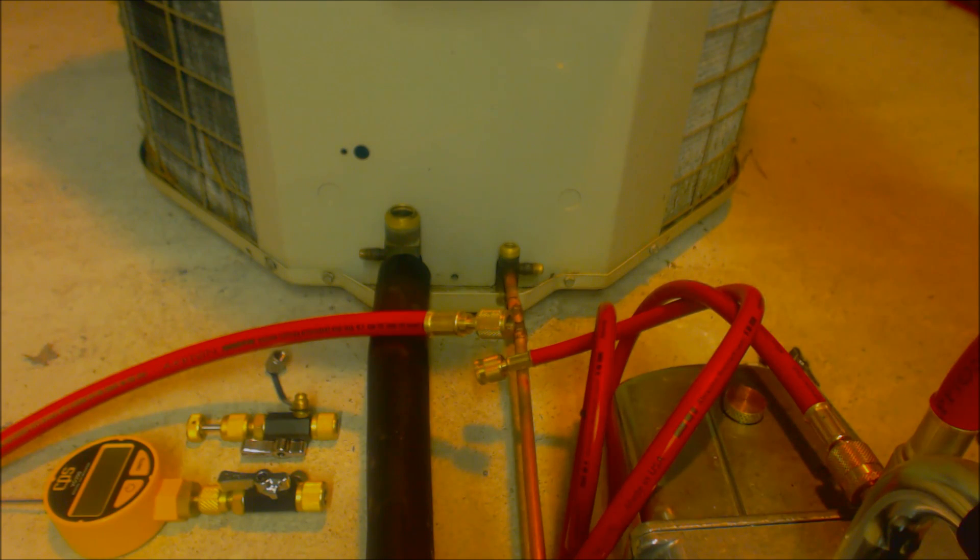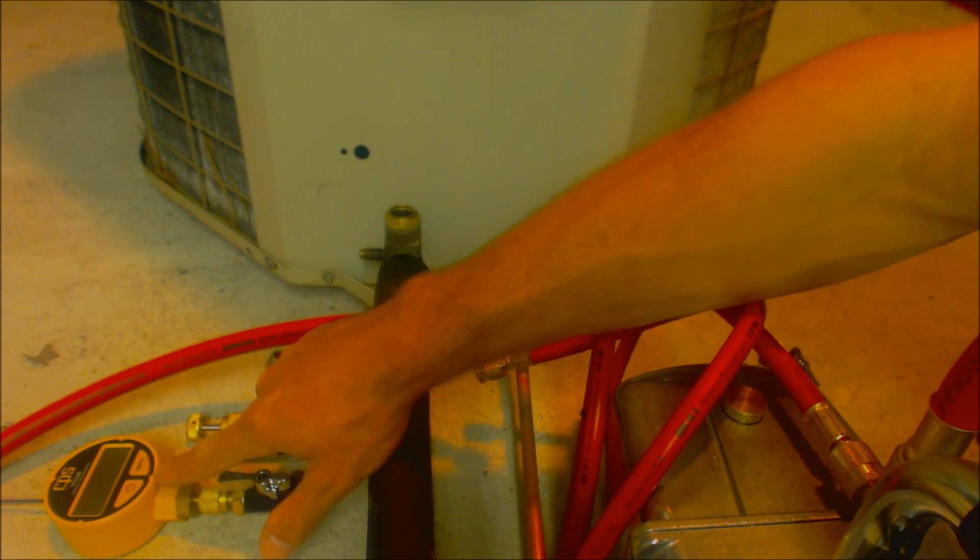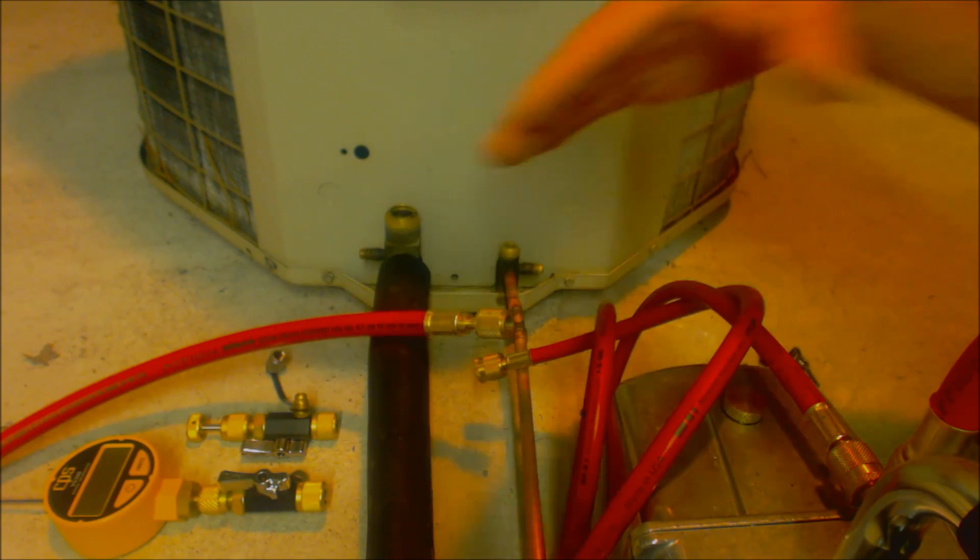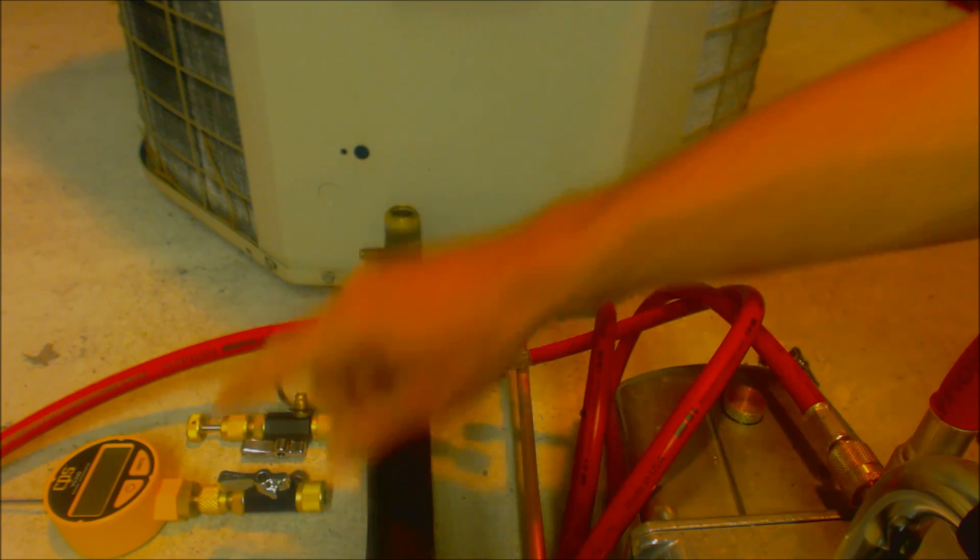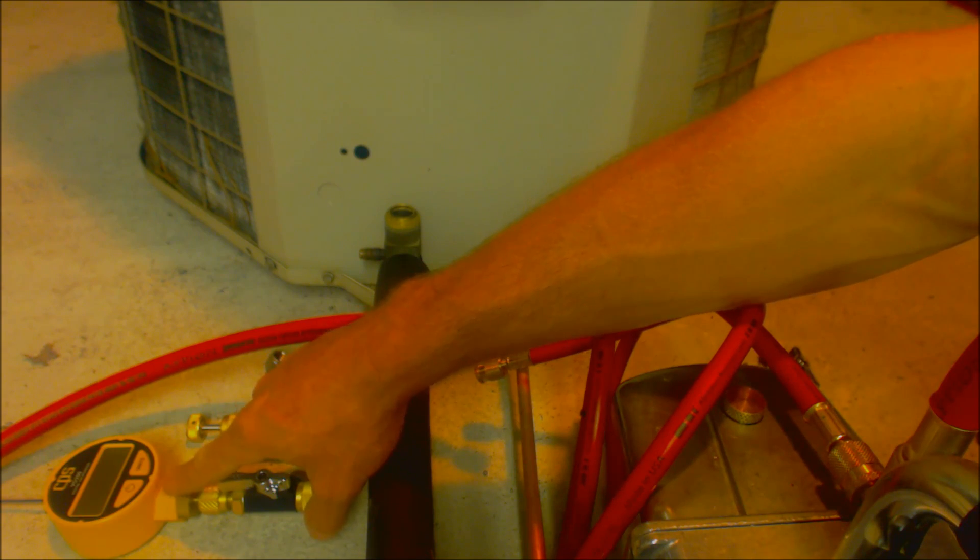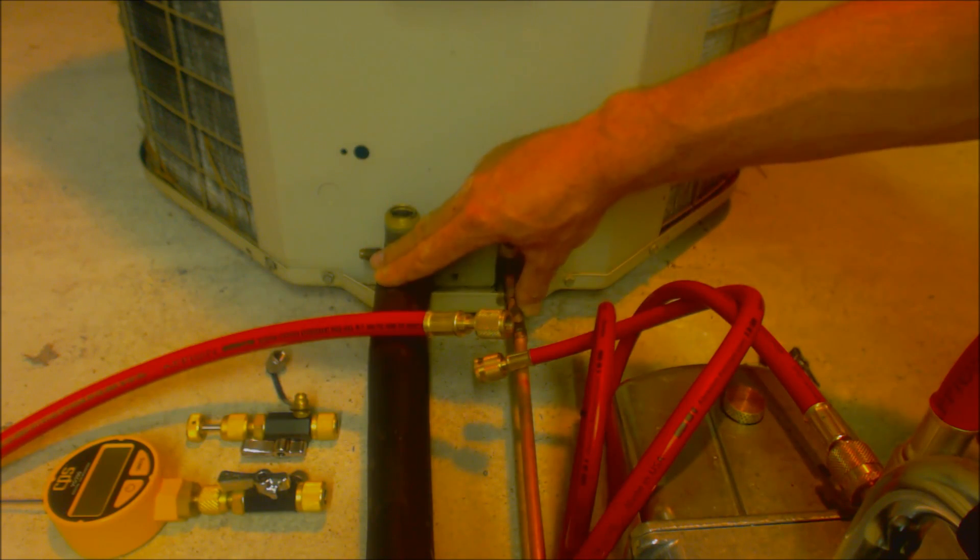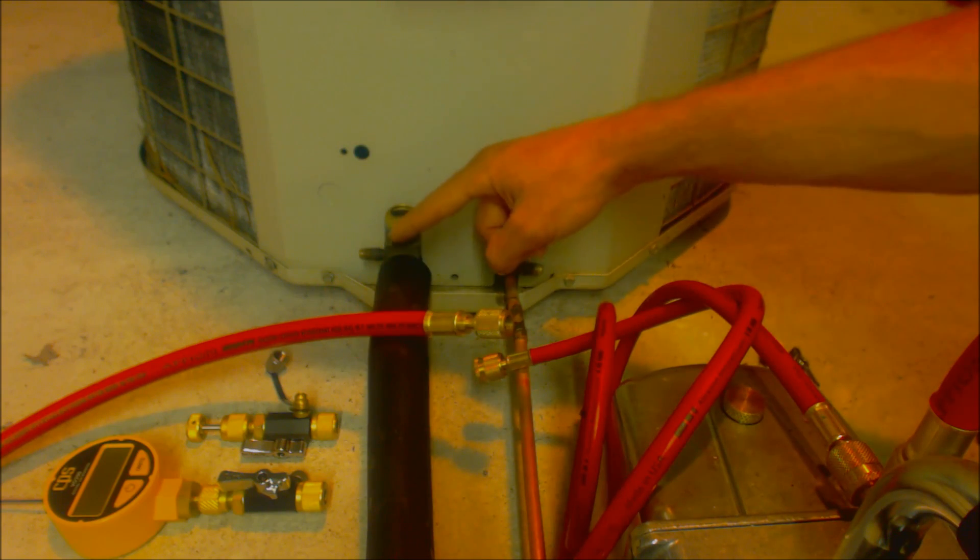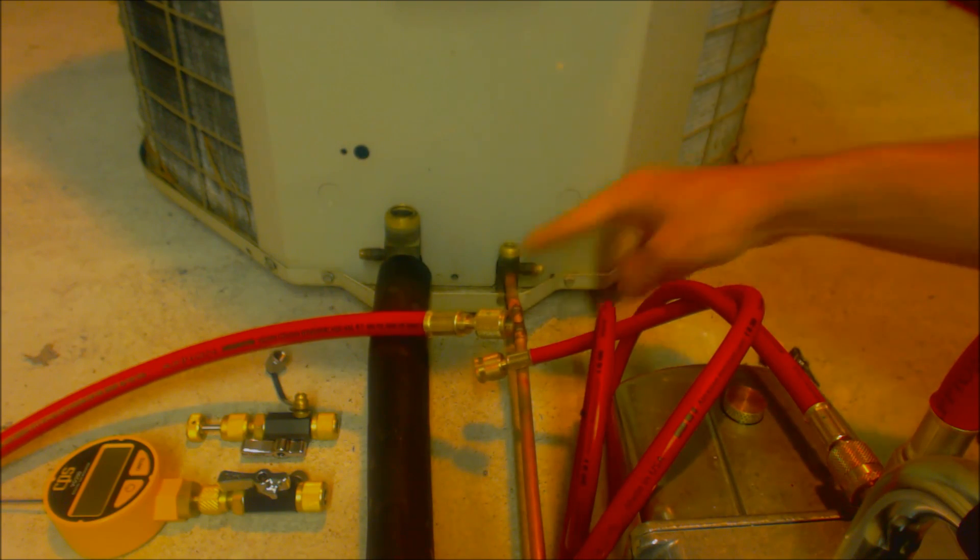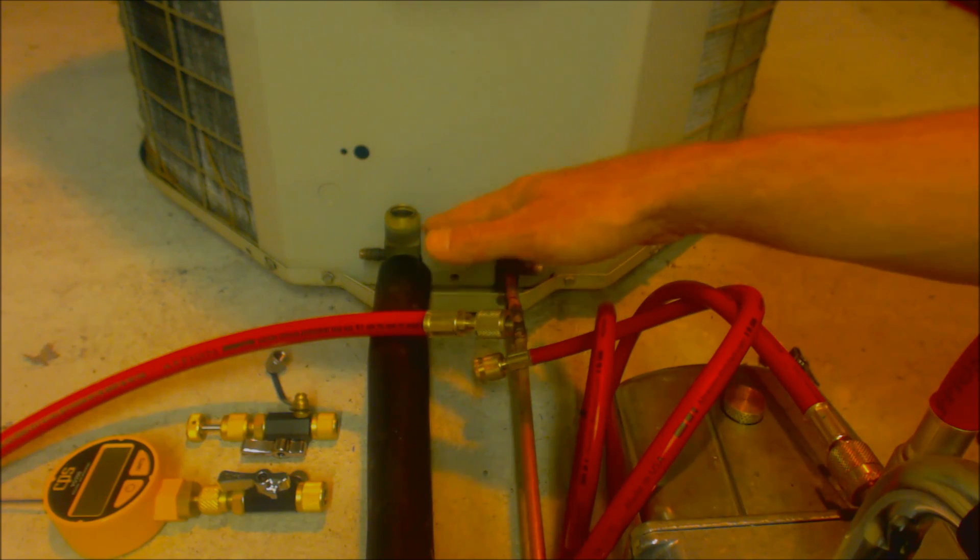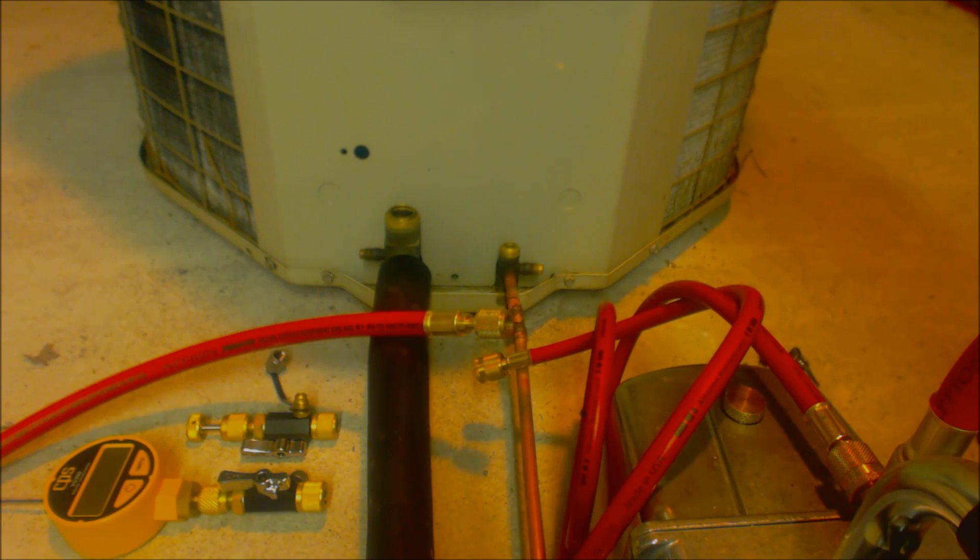So we're going to go ahead and pull a vacuum that's going to be below 500 microns on the micron scale. Then we're going to isolate the vacuum pump and the hoses, and we're still going to keep our micron gauge attached to the line set right here. During this vacuum we're vacuuming the suction line and the liquid line and the evaporator coil. We're pulling a vacuum from both sides. You always want to make sure to pull a vacuum from both sides so that you don't go through the restriction of the metering device all the way over at the evaporator coil which will be the furthest distance away.